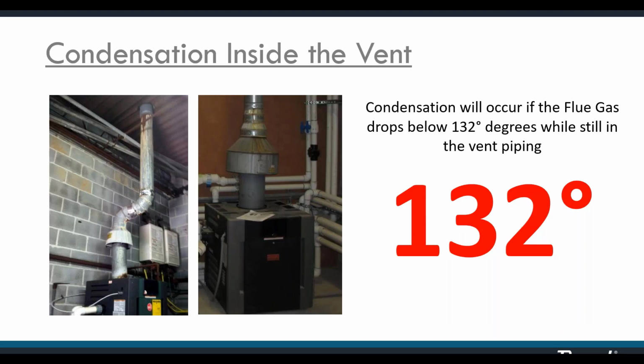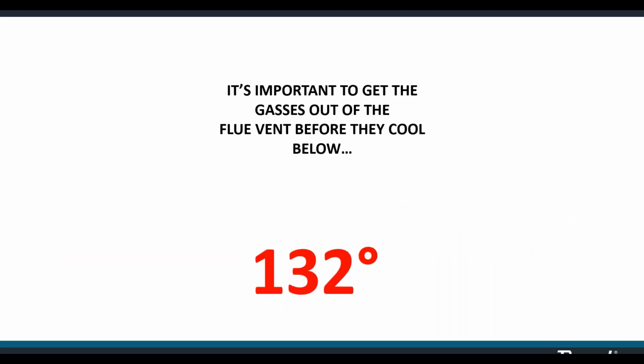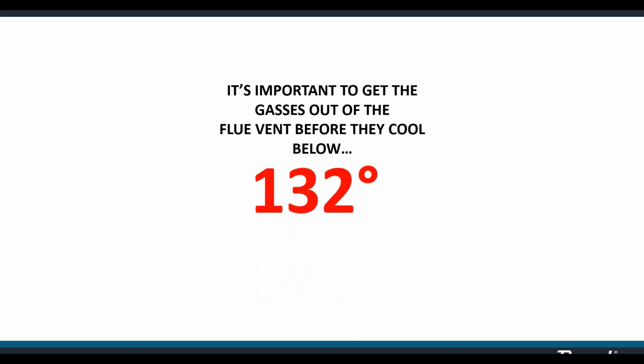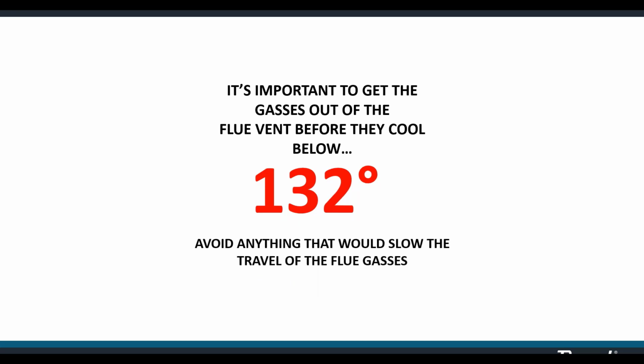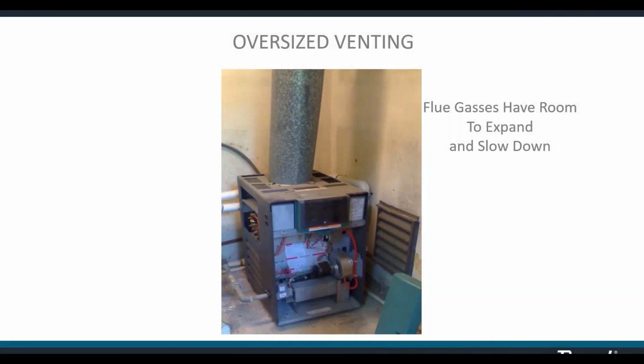As the flue gases travel through the vent, they begin to cool. If they get below 132 before they get out of the vent, condensation begins to form, and the resulting condensate not only rusts the galvanized pipe, but because it's very acidic, it can damage other parts of the heater if it runs back down. So it's important to get the gases out of the flue vent before they cool below 132. We want to avoid anything that would slow them down. Anything like, say, oversized venting. If the gases have room to expand horizontally, then they won't move as quickly vertically. We want the gases moving upward, steadily, and quickly.